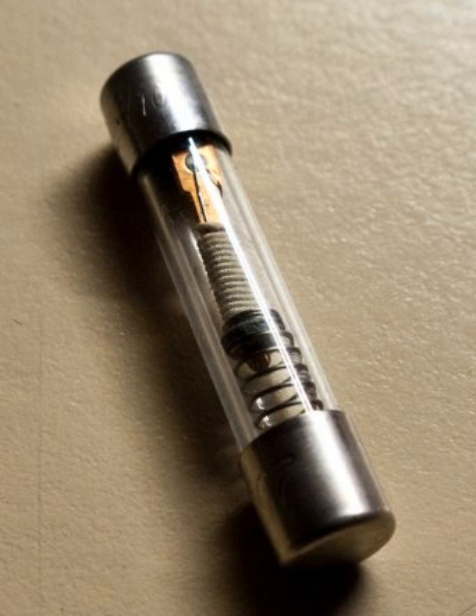Fuses have been used as essential safety devices from the early days of electrical engineering. Today there are thousands of different fuse designs which have specific current and voltage ratings, breaking capacity and response times, depending on the application. The time and current operating characteristics of fuses are chosen to provide adequate protection without needless interruption. Wiring regulations usually define a maximum fuse current rating for particular circuits.